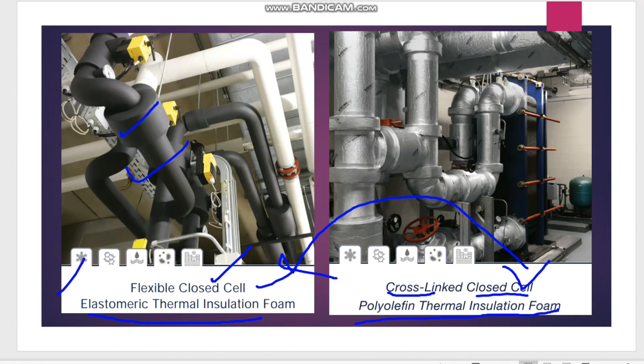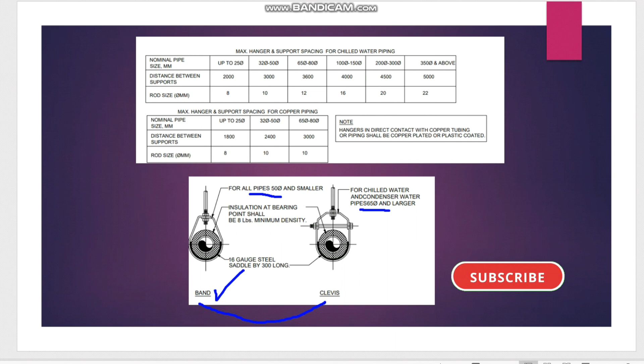Coming to the next important thing on the piping side, the support. Here I have shown two types of support. For pipe sizes less than 50 mm, we use the band hanger, and for the higher sizes, 65 mm and above, we use the most familiar one, the clevis type hanger. You can see the images here. The first image is for the chilled water piping, and the second one is for the copper piping. For carbon steel and these things, we normally use the first one. Here we have given different pipe sizes, up to 25 mm, 32 to 50 mm, until 350 mm and above. For all the sizes we have given the value.